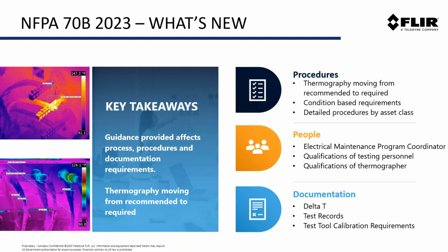While that is a mouthful, one important point to call out here is that NFPA 70E typically deals with personal safety: things like proper PPE, distance, arc flash ratings, things of that nature. 70B is really focused on the procedural aspects, as well as the levels of training and type of documentation that you need to have around your equipment.